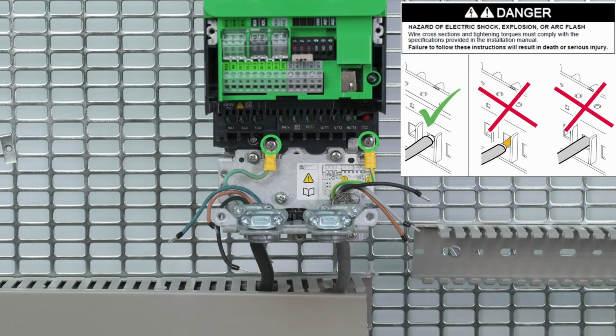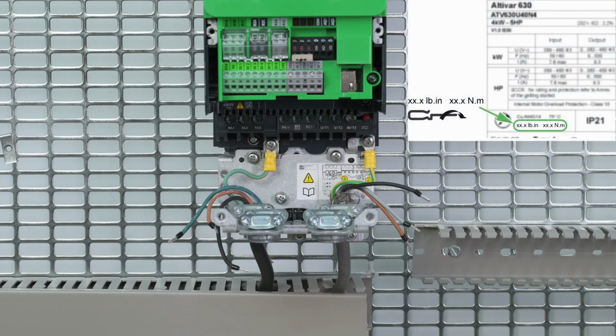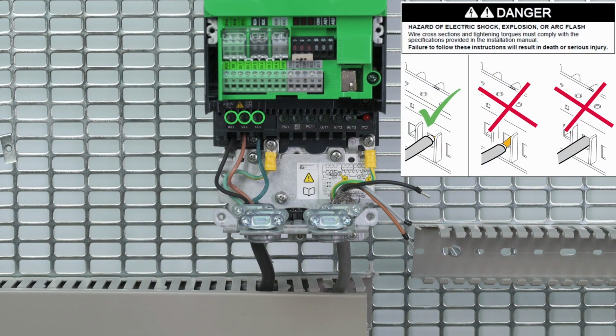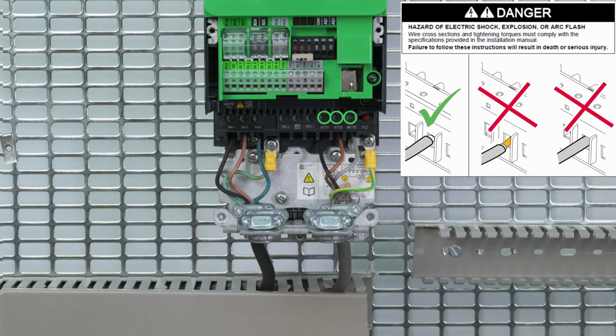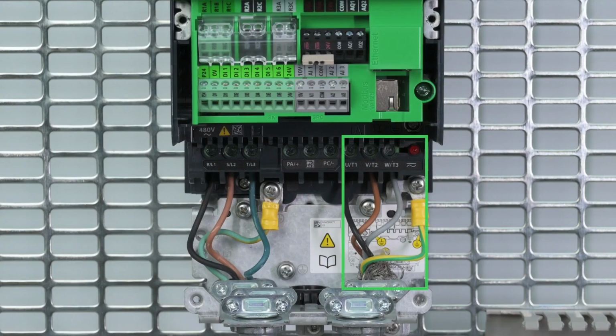We start by wiring the ground cables. For tightening torques, refer to the product nameplate or to the product installation manual. Then, the power supply connection. And finally, the motor cables. To improve electromagnetic compatibility, please use shielded cables to connect the motor to the drive.